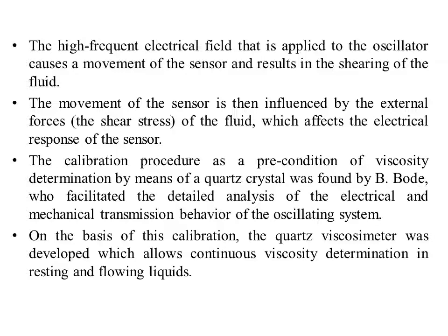The calibration procedure as a precondition of viscosity determination of the quartz crystal was found by B. Bode, who did the detailed analysis of the electrical and mechanical transmission behavior of the oscillating system. On the basis of this calibration, the quartz viscometer was developed, which allows continuous viscosity determination in resting and flowing liquids. So this can be used for continuous viscosity determination of liquids which are flowing or which are at rest.